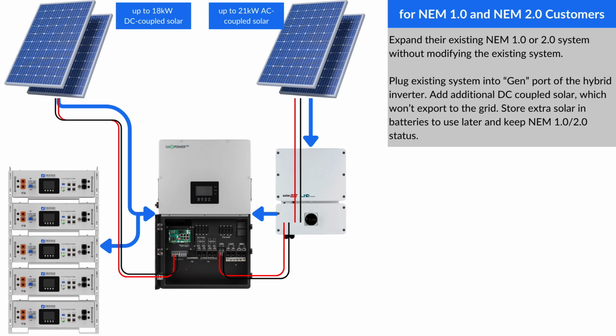The way this works is you can take the existing solar and connect it to the generator port of the inverter. Then you can add additional solar connected to the MPPTs inside the inverter.